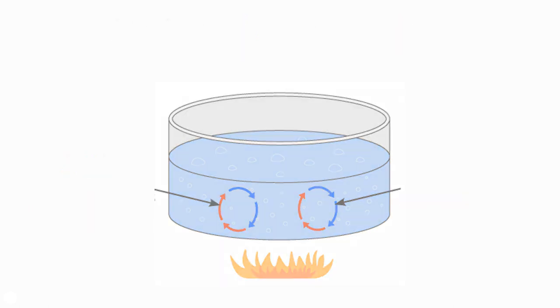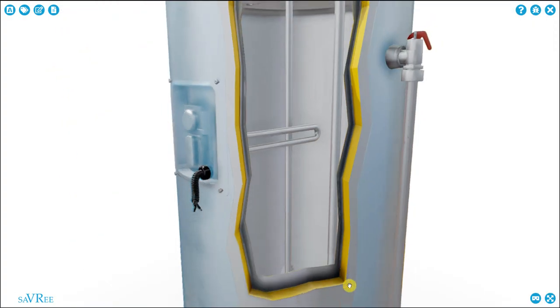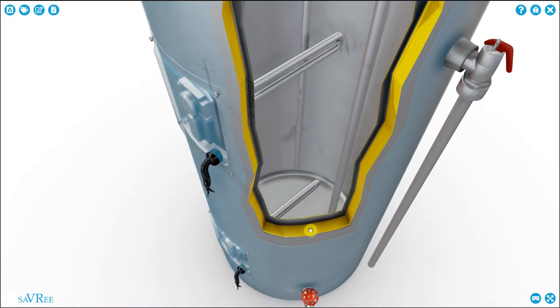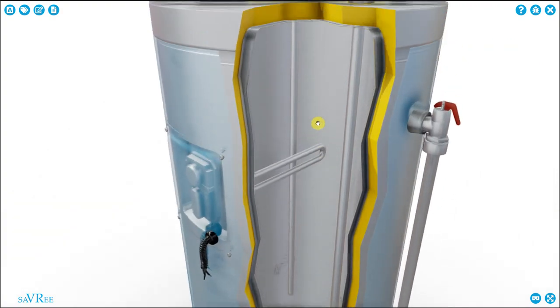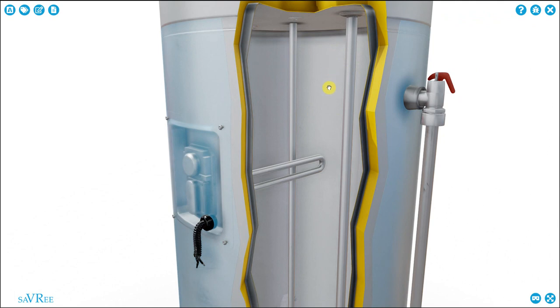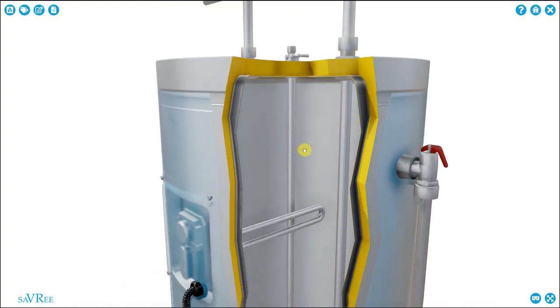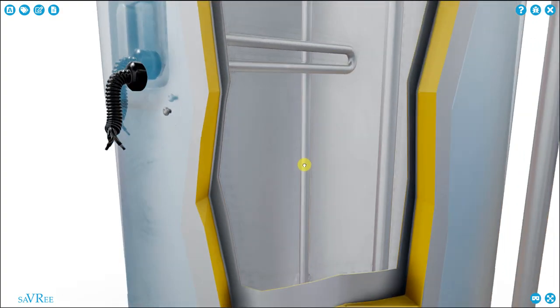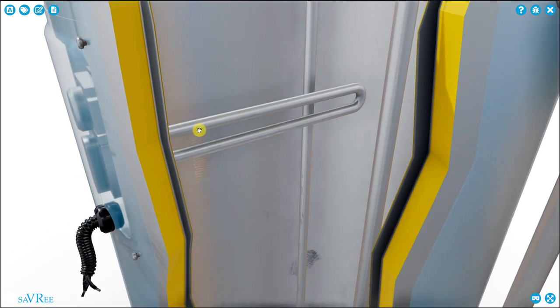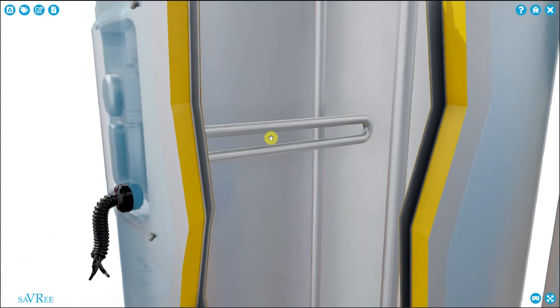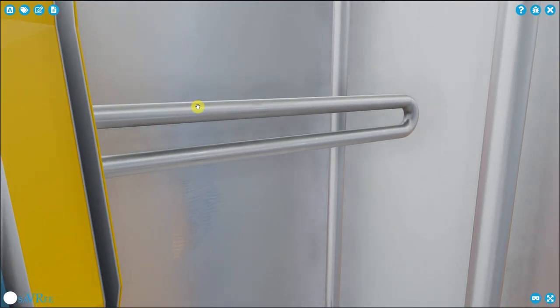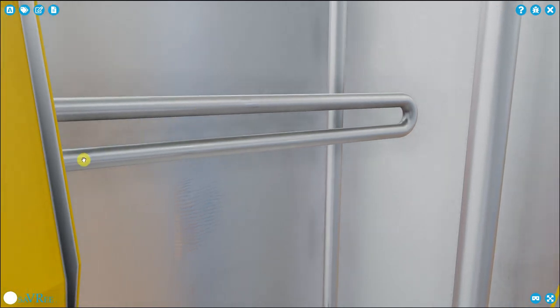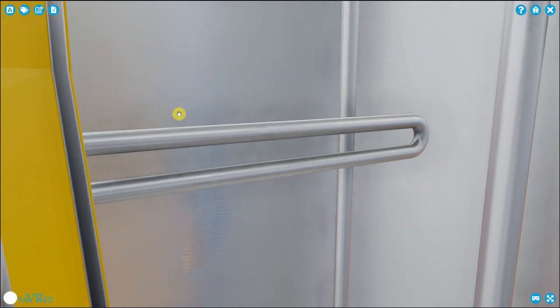Remember that usually around this heating element, there'll be water and the water gets hot and as it gets hot, its density decreases and it moves up to the top of the tank. That is natural convection. We've got a less dense, heated water rising to the top of the tank whilst our colder water will accumulate more at the bottom of the tank. It's another reason for having the dip tube. It's because the water will be heated up from the bottom and it will naturally rise upwards. If we were putting cold water into the top of the tank, it would be moving down as the hot water was trying to move up and get out of the tank. And that's quite an inefficient way to design our water heater. So if we have this calc, also known as scale, building up on our heater elements, then we're going to end up with potentially ruptured heater elements. In addition to that, we're going to end up with quite large electricity bills because we're providing the electricity to our resistor element, but it's not heating up the water because this layer of thermal insulation has built up on the heating element.